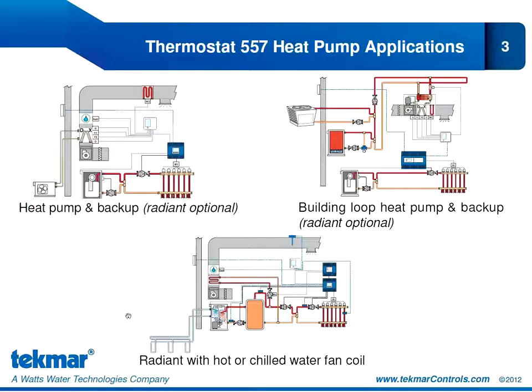Our last heat pump application shows a water-to-water heat pump in line with a buffer tank. In this case, if we're in heating mode, we can provide 1st stage heating through our radiant system. Our 2nd stage of heating would be provided from the fan coil. And if we switch over to cooling mode, then our 1st stage of cooling would be through our fan coil. And here we have the option of doing radiant floor cooling. And in this webinar presentation, we'll explore how the 557 is perfectly positioned to accommodate designs that include radiant floor cooling.